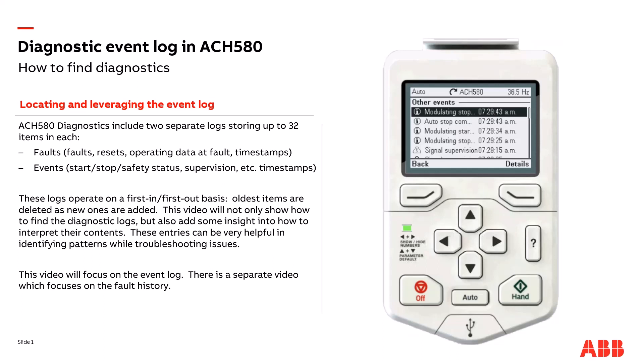In wrapping up, I'd like to mention an actual scenario where use of the event logger would have been instrumental. I got a call from one of our reps supporting a tech on-site starting up fans for the first time. The issue was that the drive output contactor kept opening every time the drive attempted to start — on more than one drive. These were BCR bypass units using BACnet. No warnings were being reported on either the bypass or drive displays. I suggested disconnecting the comms connection to rule out something BACnet-related, yet the problem persisted. All the wiring to the unit and motor was rechecked and confirmed okay.